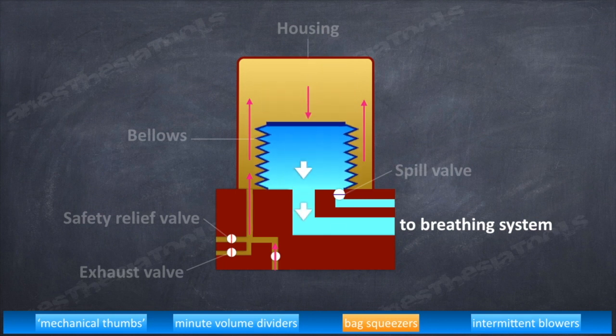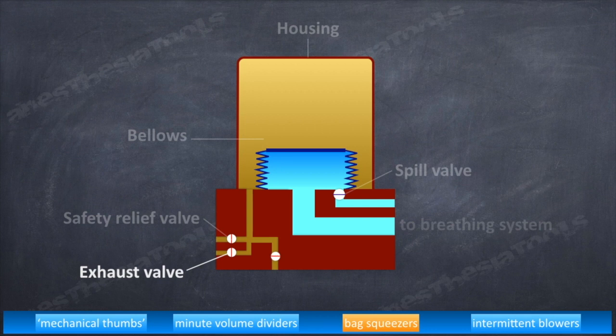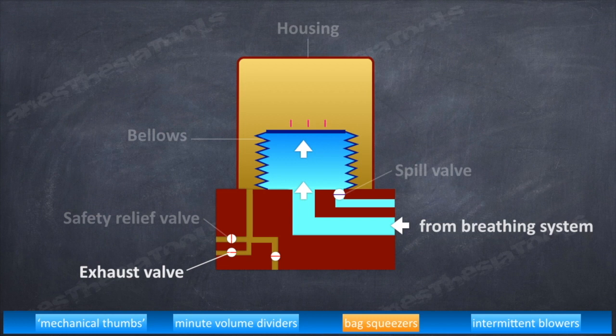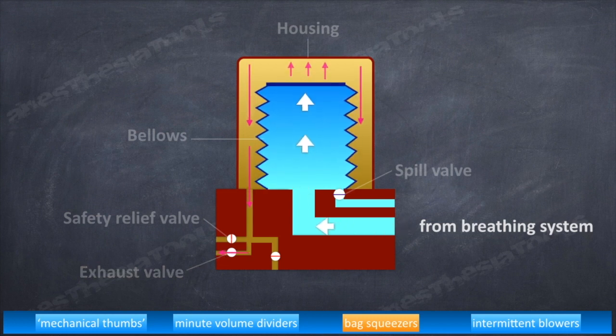We can regulate the parameters like tidal volume, respiratory rate in bag squeezer type of ventilators. Within respiratory rate, I:E ratio or inspiratory flow and inspiratory time can be set by the operator.